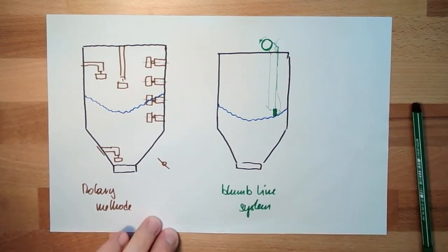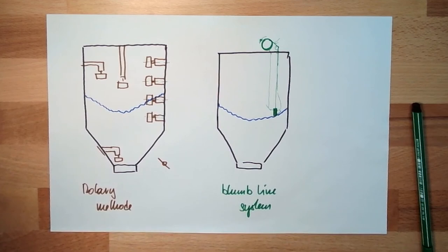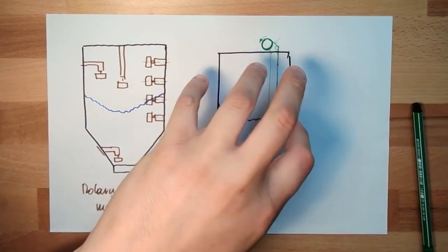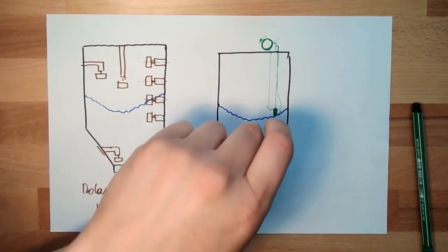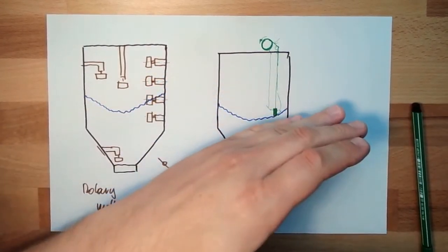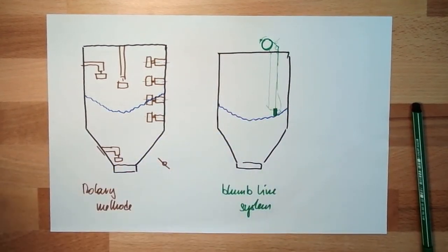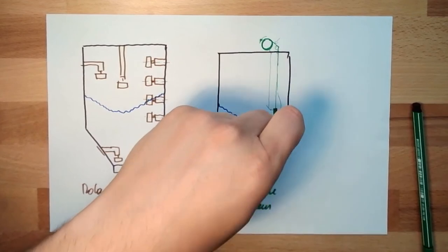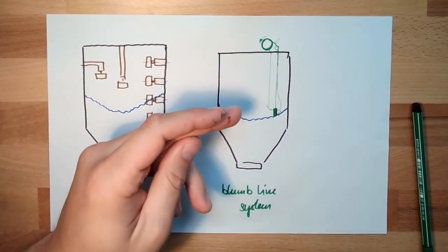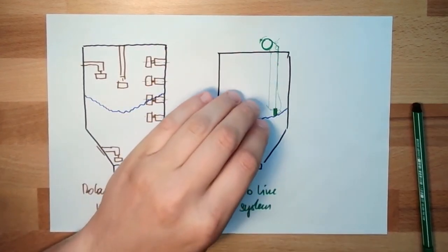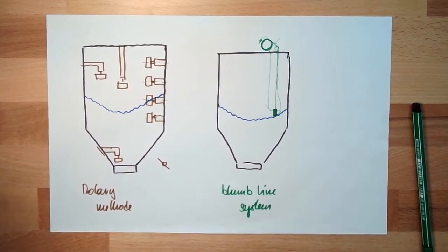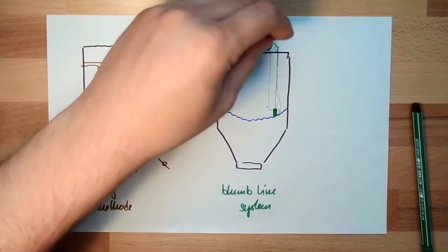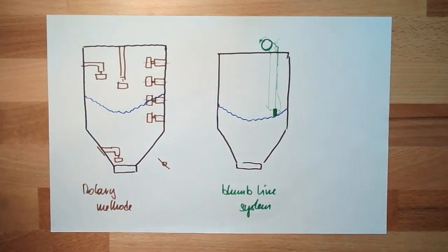The big advantage is I can use this with really big tanks — no issue; I can spool it down 70 meters. It doesn't really care which material is below — gravel, sand, it doesn't matter — I just have to hit the surface. Disadvantage: it needs maintenance, and of course it's not a continuous measurement; it takes a while to get a reading. So if it's highly dynamical, this is not the correct method.